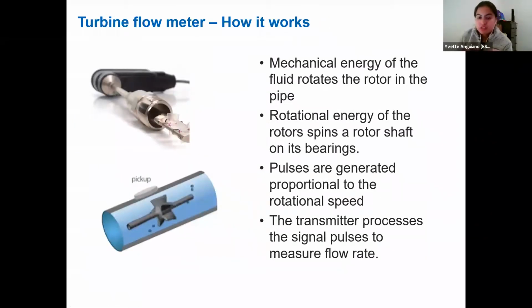As we touched on, this device works with rotational parts. As the water flows, it starts to rotate these rotors here, and the rotational energy creates pulses that are then measured, and the transmitter processes the signal pulses to determine the flow rate.